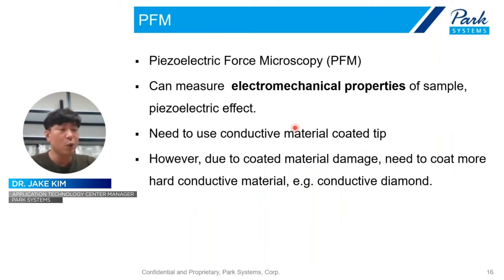Next is the PFM, the piezoelectric force microscope. Using PFM, we can measure the electromechanical properties, simply speaking, the piezoelectric effect. And of course it is an electrical property measurement, so we need to use a conductive material coated tip. But actually EFM and KPFM are non-contact mode based, while PFM is contact mode based, so we should apply a harder conductive material like conductive diamond. Of course, we can use a gold coated tip, but due to this contact mode, that gold coated layer can be easily disappeared or damaged.